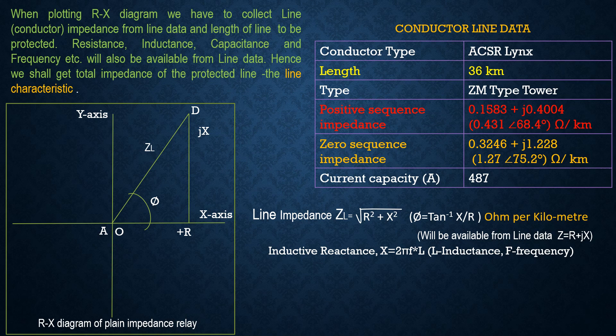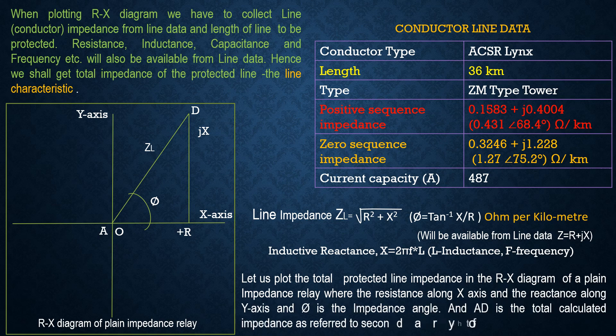Total impedance is calculated for the 36 km line length based on positive sequence impedance for phase-to-phase faults, and on zero sequence impedance for earth faults. The relay calculates everything based on data input. We then plot the total protected line impedance on the RX diagram of a plain impedance relay, with resistance along the X-axis, reactance along the Y-axis, φ as the impedance angle, and AD as the total calculated impedance referred to the secondary of the protected line.